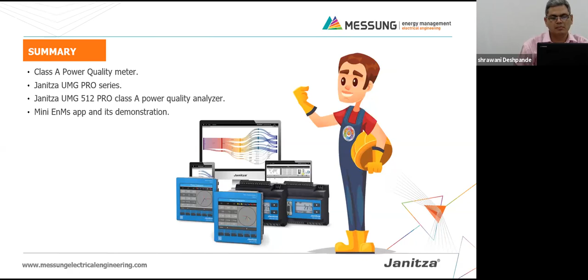Yes, sir. See, the moment IEEE 519 becomes an ordinance in Maharashtra or any state, automatically they will put in that sub-standard which I put on your chat box. IEC 61000-4-30 standard comes. And the moment Janitza gets their meters approved for that standard, assume that the readings are going to be accepted. Same thing Schneider also does.